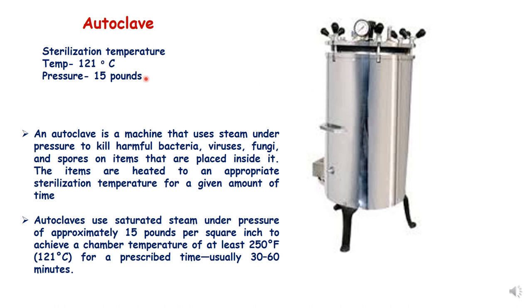The sterilization temperature is generally 121 degrees Celsius, and the pressure maintained inside the autoclave is 15 pounds per square inch. Autoclave uses saturated steam under approximately 15 psi to achieve 121 degrees Celsius or 250 degrees Fahrenheit for a prescribed time — generally 15, 30, or 60 minutes, depending on the autoclave model and manufacturer specifications.